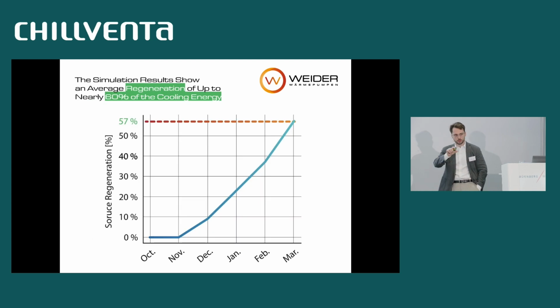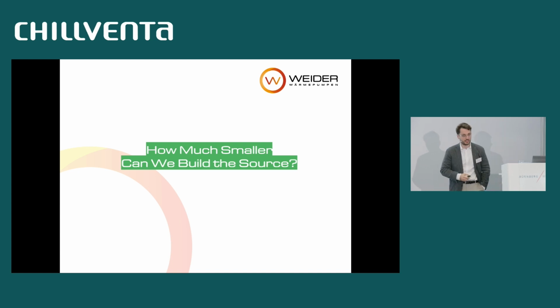And if you want to compare now how much we can actually restore during the heating period, in this case, if you sum up all the orange bars from the previous plot and compare the regeneration energy to the cooling energy from the source, we end up restoring almost 60% of energy during the heating period on average over the last 10 years. Now the burning question is how much smaller can we actually build the source?